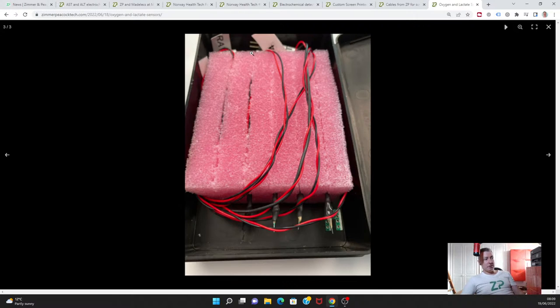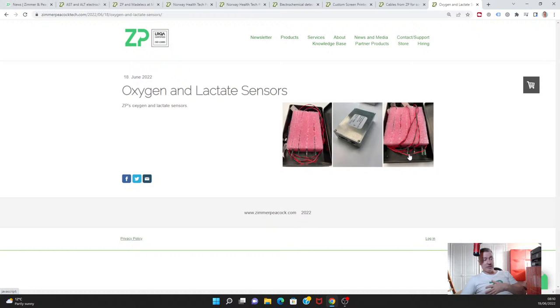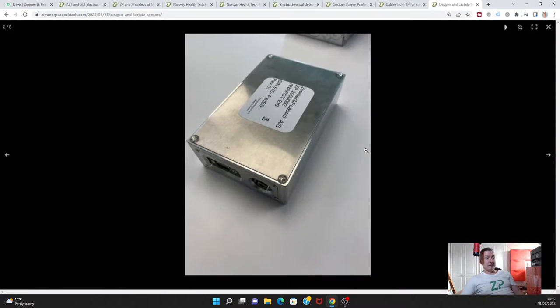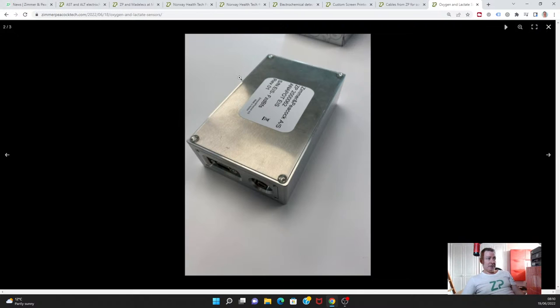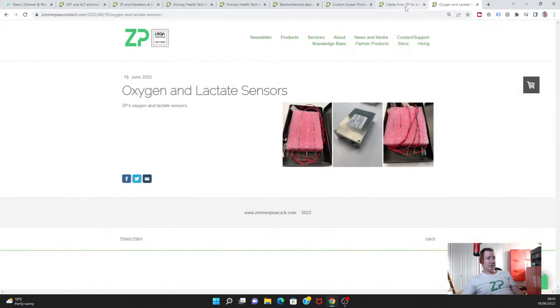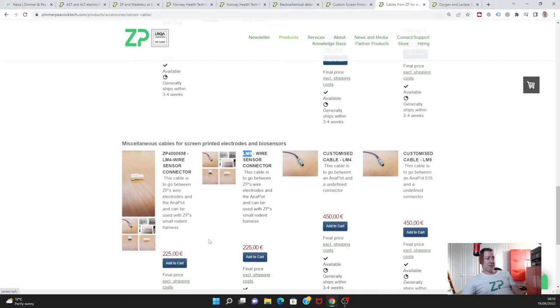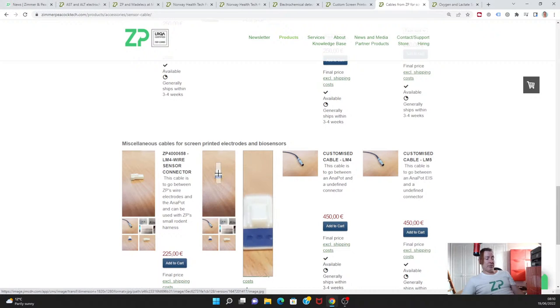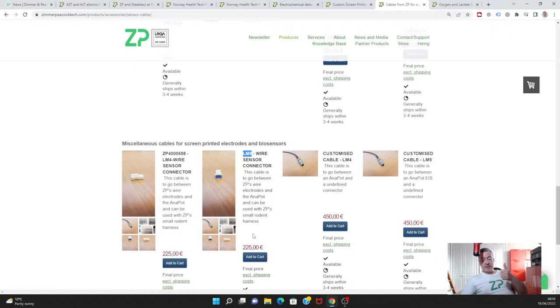This is the proximal or sensing end. There's also a distal end where there's like just a couple of prongs. These couple of prongs are making electrical contact. When I look at the images that have been sent, I see the sensors and there are two electrodes on those sensors, and I see the instrument itself. The instrument itself has a connector on it, a circular connector. It has five holes in that connector, so it's a five-pin Lemo connector. What I don't see in the photographs that's been sent to us is a special cable that will work with a Lemo five-pin and has a special plastic part that will connect with the sensors itself. So I feel like something's missing from the box.